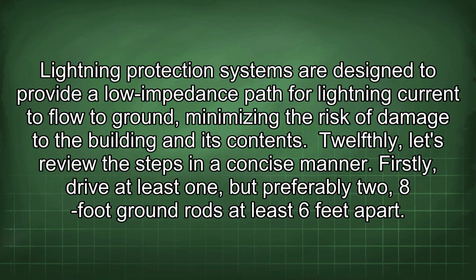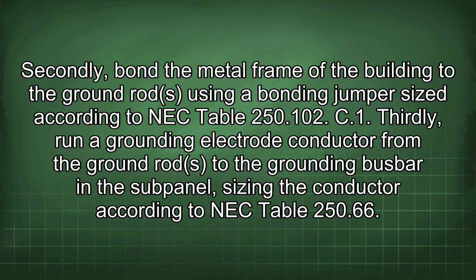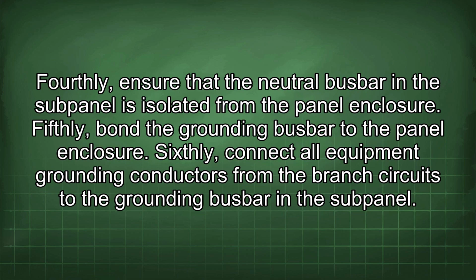12thly, let's review the steps in a concise manner. Firstly, drive at least one, but preferably two, 8-foot ground rods at least 6 feet apart. Secondly, bond the metal frame of the building to the ground rods using a bonding jumper sized according to NEC Table 250.102(C)(1). Thirdly, run a grounding electrode conductor from the ground rods to the grounding busbar in the subpanel, sizing the conductor according to NEC Table 250.66. Fourthly, ensure that the neutral busbar in the subpanel is isolated from the panel enclosure. Fifthly, bond the grounding busbar to the panel enclosure. Sixthly, connect all equipment grounding conductors from the branch circuits to the grounding busbar in the subpanel.